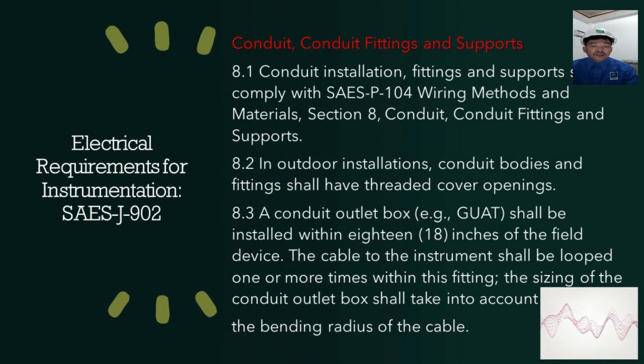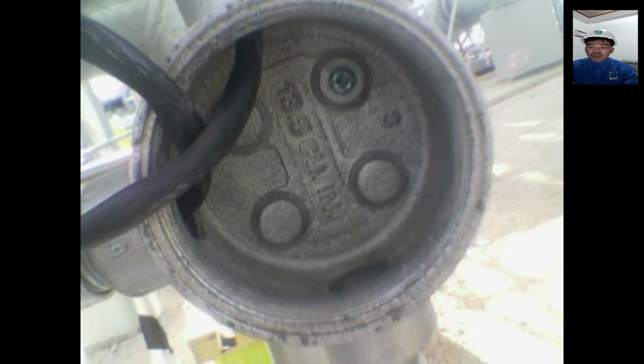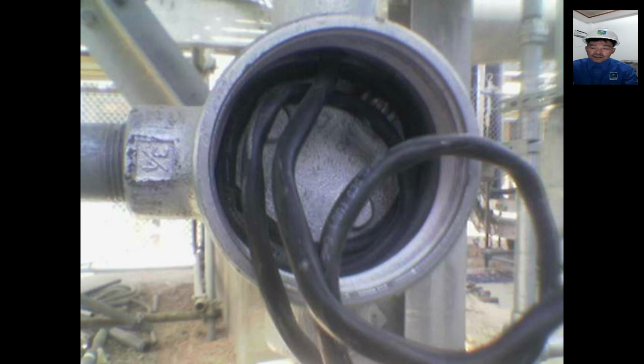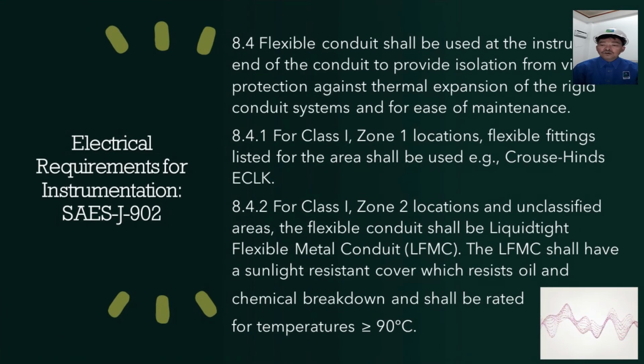Conduit and conduit fittings and supports are all under SAES-P-104. We have discussed these things in SAES-P-104. You can read it in section 8. In outdoor installations, conduit bodies and fittings shall have threaded cover openings. A conduit outlet box shall be installed within 18 inches of the field device. The cable to the instrument shall be looped one or more times within this fitting. The sizing of the conduit outlet shall take into account the bending radius of the cables. Flexible conduit shall be used at the instrument end of the conduit to provide isolation from vibration, protection against thermal expansion of the rigid conduit system, and ease of maintenance. So these are the reasons why we need the flexible conduit.